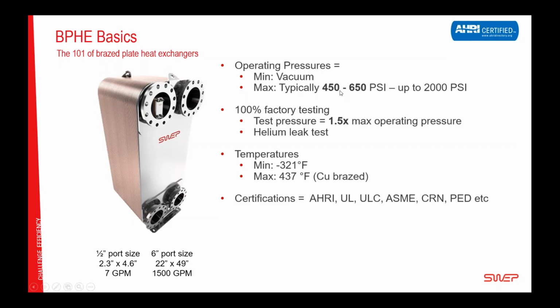The maximum pressure is, depending on model, 450 psi to 650 psi. SWEP also has high pressure or really high pressure units up to 2000 psi working pressure for transcritical CO2. Another thing we do with all our heat exchangers is 100% factory testing. So before shipping them to our customers, we have a test pressure that is 1.5 times the operating pressure. If the heat exchanger can take that, we then test it and see that it's not leaking to make sure that it adheres to the requirements that we have.